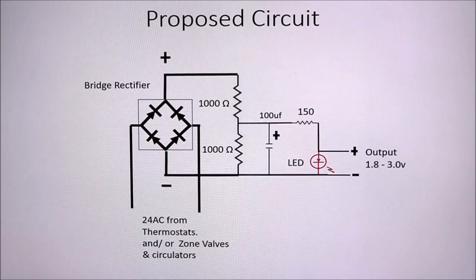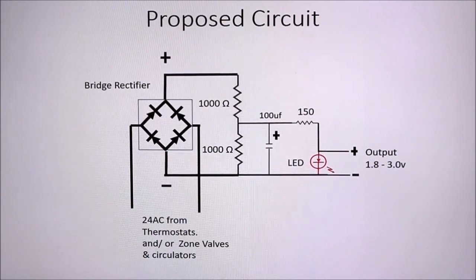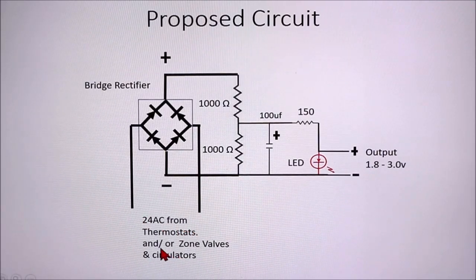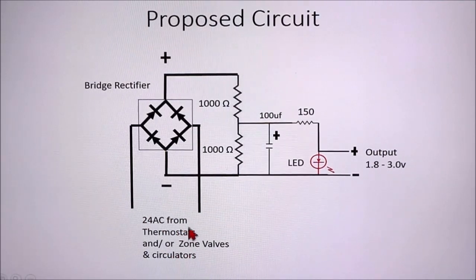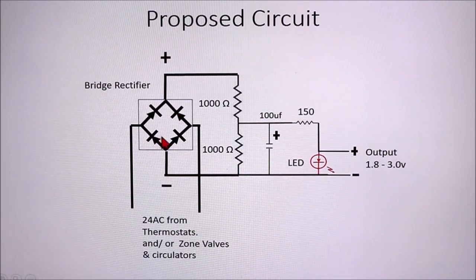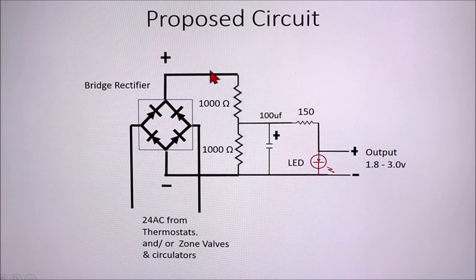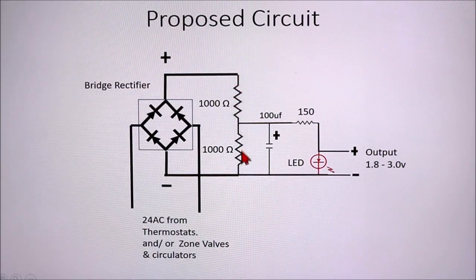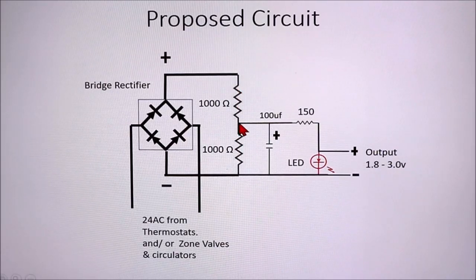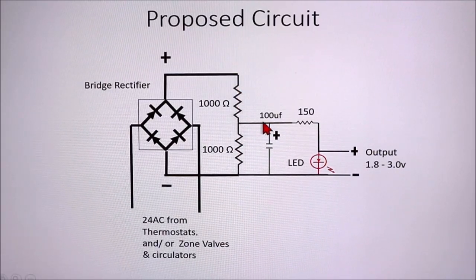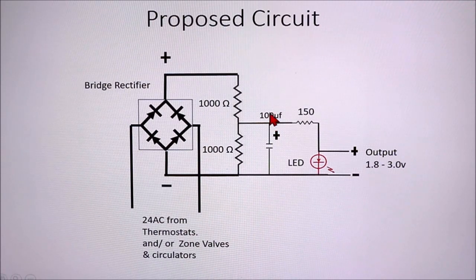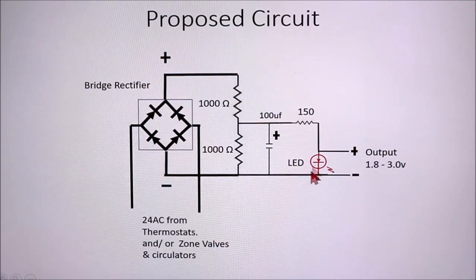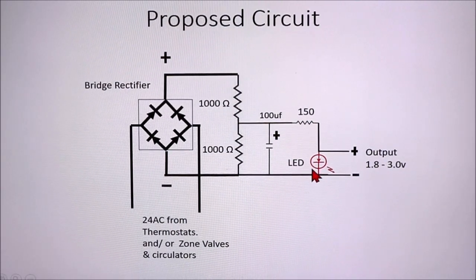So this is the circuit I came up with. It's pretty simple and easy to implement. Over here we have the 24 volts AC from the thermostats or zone valves or circulators. We run that 24 volts AC through a bridge rectifier to convert it to DC. And then we reduce the voltage with these two 1,000 ohm resistors, which cuts the voltage in half. So now the rectified DC is put through a filter capacitor, 100 microfarads, and then 150 ohm resistor and an LED.